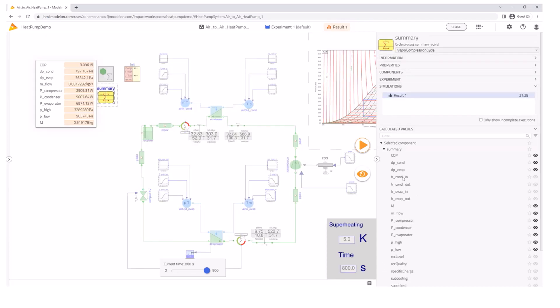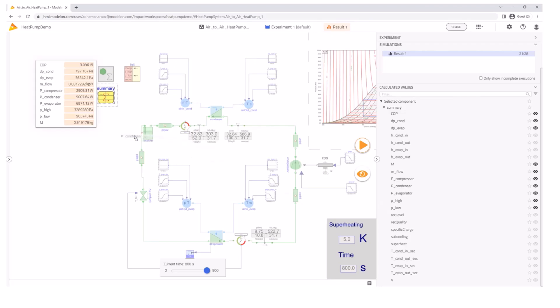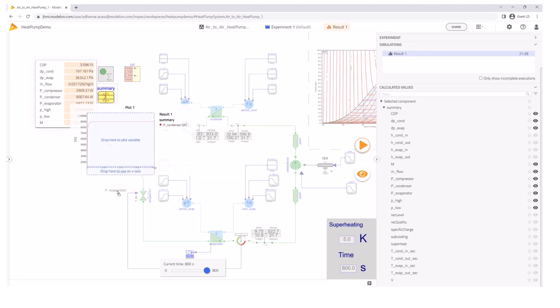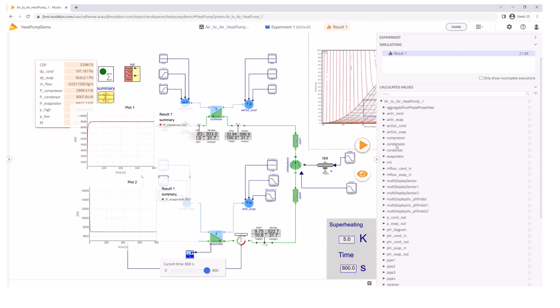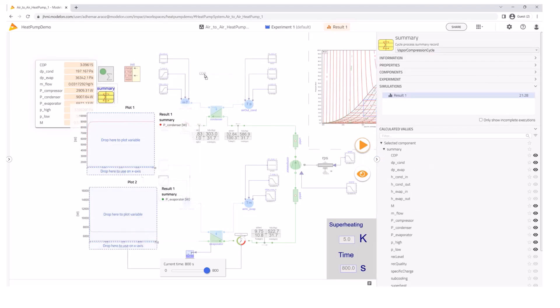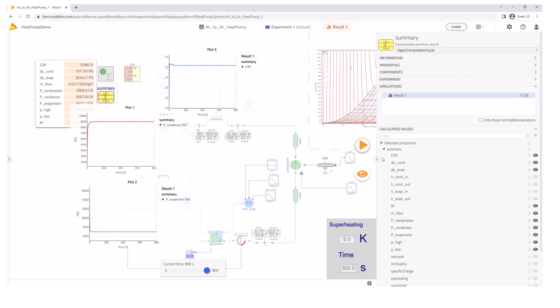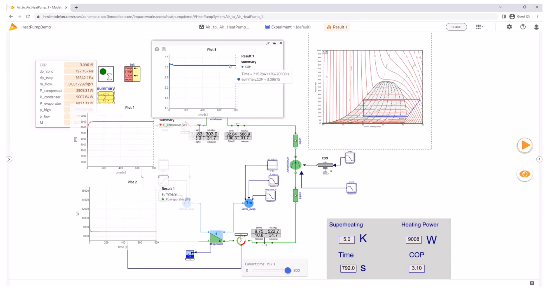I can also plot the trajectories for these variables by a simple drag and drop onto the canvas. I plot, for example, the power for the condenser and evaporator, and I also plot the COP trajectories. Additionally, I can track how the cycle evolves during the simulation using the pH diagram and the time slider. The simulation reaches a COP of 3.06 — let's see if we can improve it.